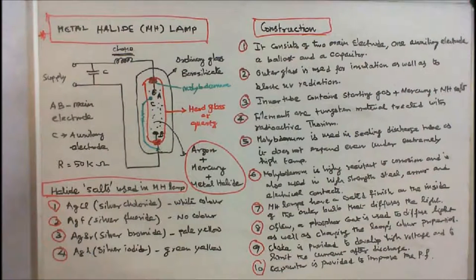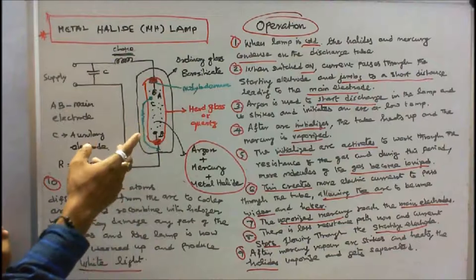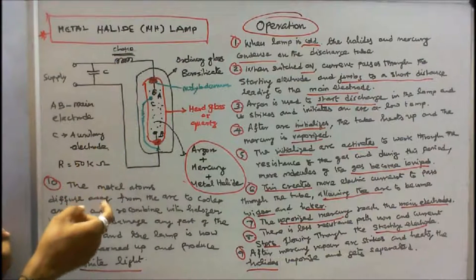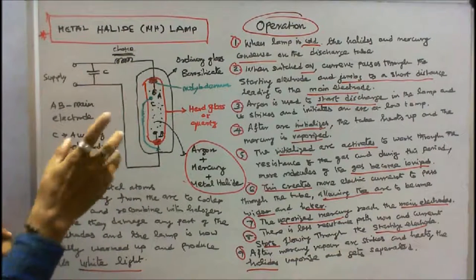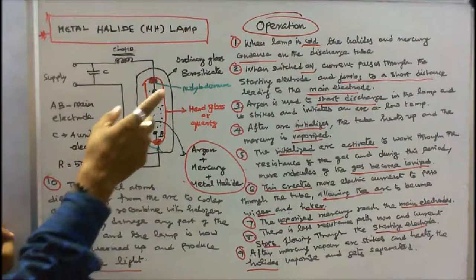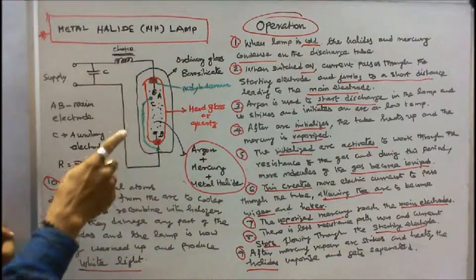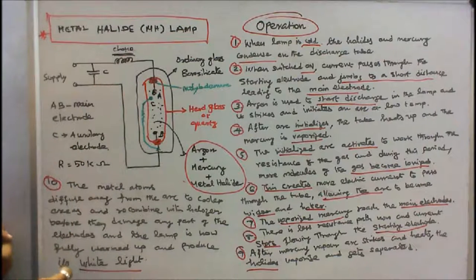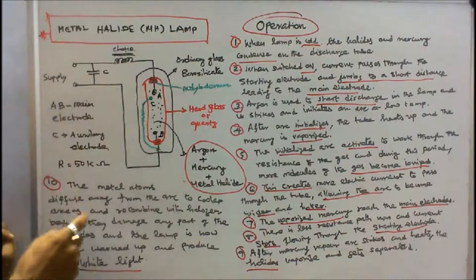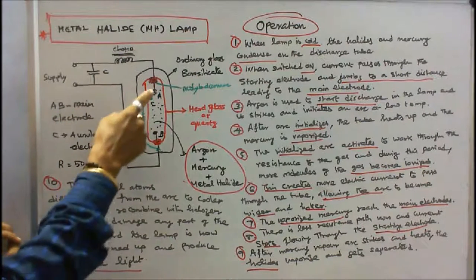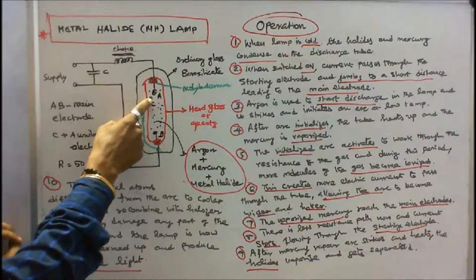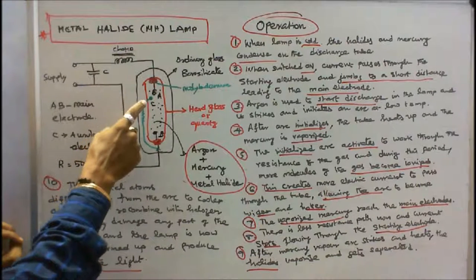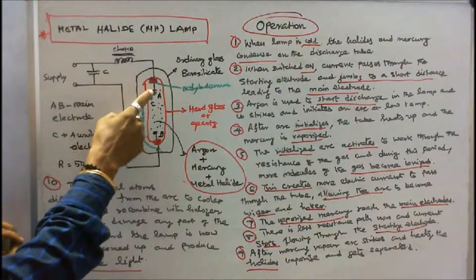Now we see the operation of metal halide lamp. When lamp is cold, the halides and mercury condense on the discharge tube or inner tube. When the supply is switched on, current passes through the starting electrode or auxiliary electrode and jumps a short distance leading to the main electrode.